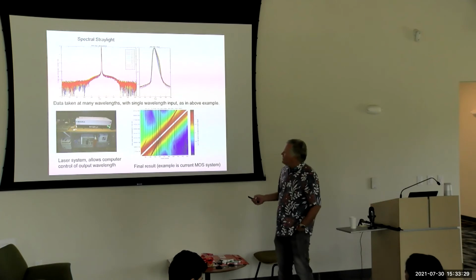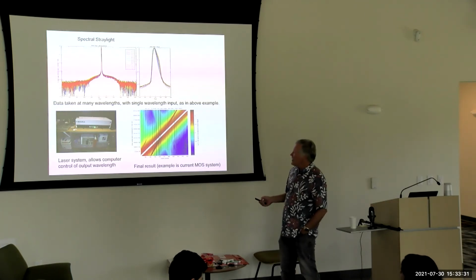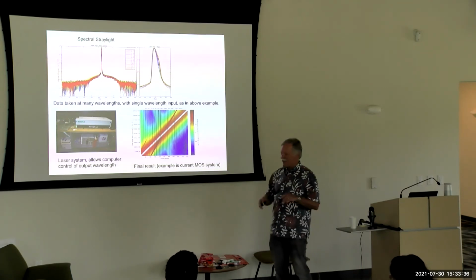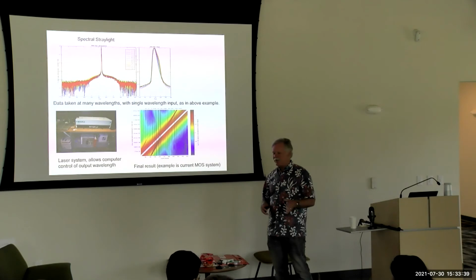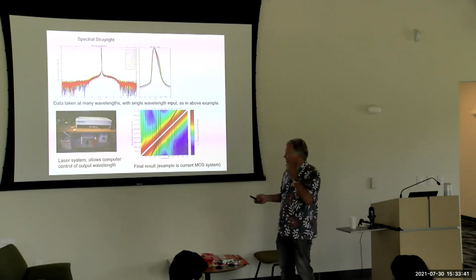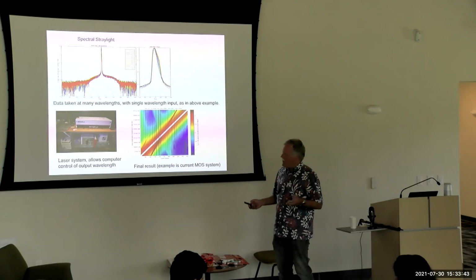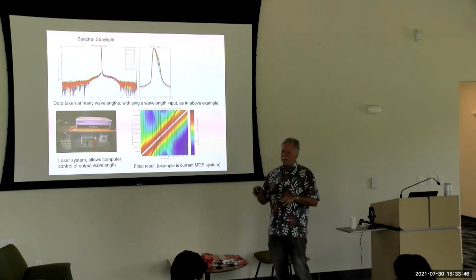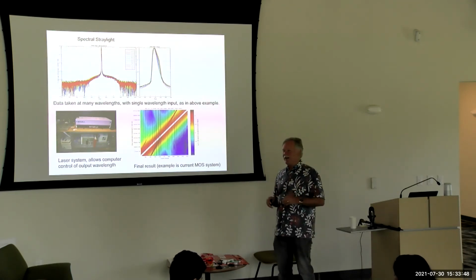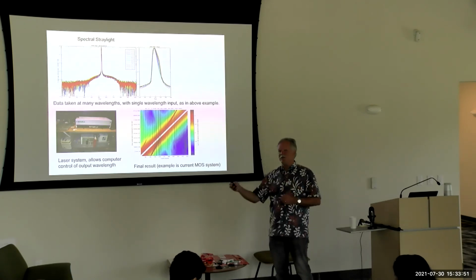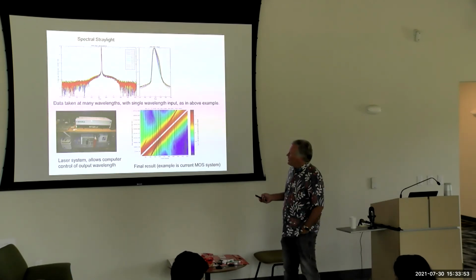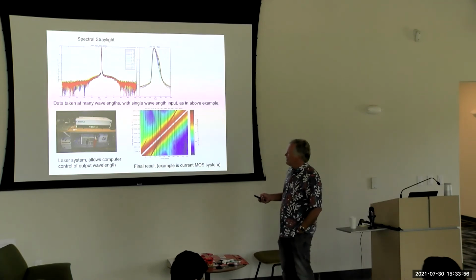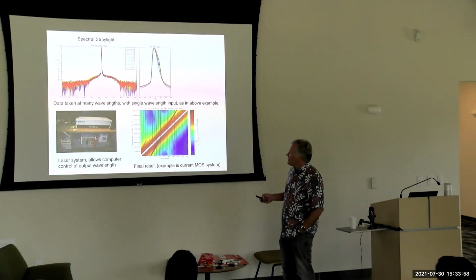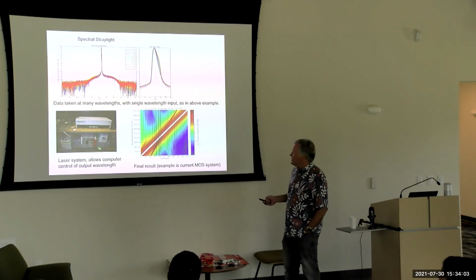So here's the laser. This is the thing I was telling you, it's computer controlled. You say the wavelength you want, from 200 to 1200 nanometers, something like that. You say I want 340 nanometers, and it calculates and figures out how to move a bunch of crystals inside and how much of this pump laser to use versus that pump laser to use. It's really, really cool. Anyway, it generates whatever wavelength you want. We use this to do the stray light characterization. We don't have to go to NIST now.